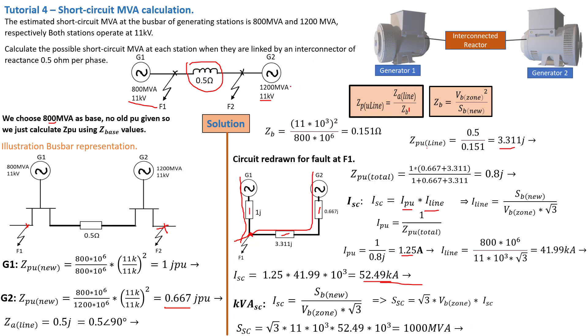Remember, the problem stated an estimated short circuit MVA of 800 MVA on this side. But when we calculate, we're getting 1000 MVA — precisely because generator 2 is also contributing now. Fortunately, the reactor is dampening the contribution from G2, limiting the short circuit current coming from that side. If we repeat this calculation without the reactor, this value would be very high. You can try that exercise — you'll get a short circuit MVA of 2000 MVA, which is 800 plus 1200 MVA.